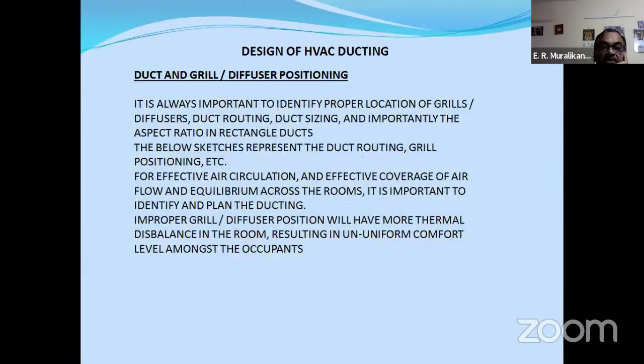Now, duct and grill diffuser positioning. It is always important to identify the proper location of grills, diffusers, duct routing, duct sizing, and importantly, the aspect ratio. Just a few minutes back, I told you how the duct sheet size changes just because we have changed the aspect ratio. Instead of 22 gauge, we are going for 28 gauge or some up or down gauge because the aspect ratio is not proper.